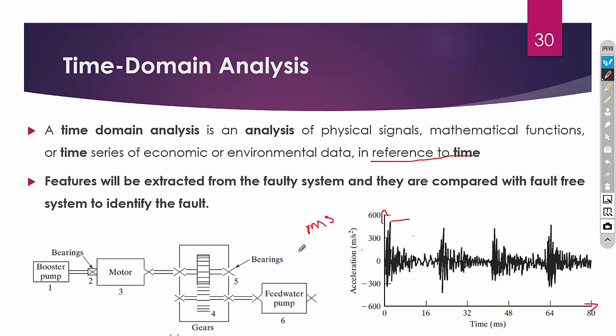The most important time domain feature used in machinery fault diagnosis is the RMS — root mean square value. For example, we extract the RMS value and compare it against a reference for the healthy condition, say 0.9 meters per second squared. We continuously take the vibration signal and calculate the RMS value. When the RMS value exceeds 0.9 meters per second squared, it means vibration levels are high and we need to focus on fault identification.